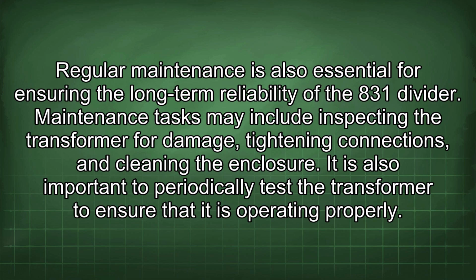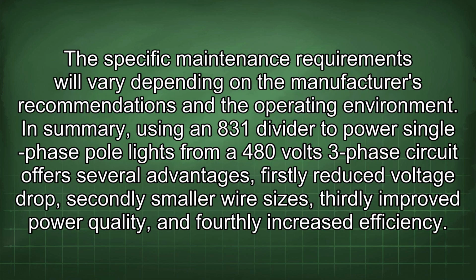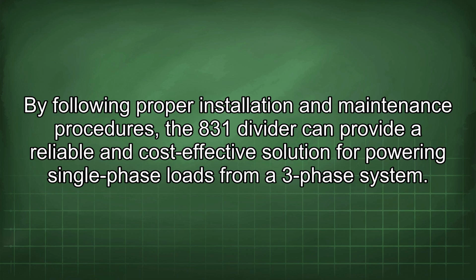Regular maintenance is also essential for ensuring the long-term reliability of the 831 divider. Maintenance tasks may include inspecting the transformer for damage, tightening connections, and cleaning the enclosure. It is also important to periodically test the transformer to ensure that it is operating properly. The specific maintenance requirements will vary depending on the manufacturer's recommendations and the operating environment. In summary, using an 831 divider to power single-phase pole lights from a 480 volts three-phase circuit offers several advantages. Firstly, reduced voltage drop. Secondly, smaller wire sizes. Thirdly, improved power quality. And fourthly, increased efficiency. By following proper installation and maintenance procedures, the 831 divider can provide a reliable and cost-effective solution for powering single-phase loads from a three-phase system.